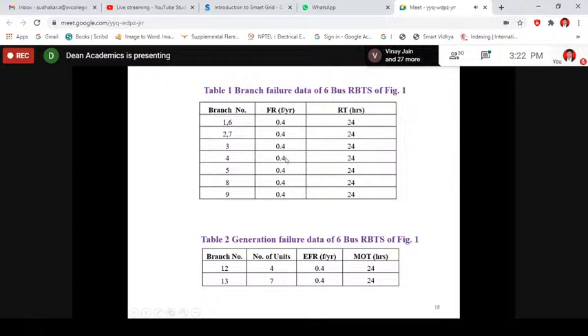Anyway, this is the estimated assumed value, and this is also the repair time for certain transmission lines. People may say 1 or 2 hours, but practically, if it fails in the evening, no repair will come immediately. You may have to wait around 12 hours until the next day when the lineman or electricians arrive, cut supply to the other zone, and so on. We are not doing live replacement here, although it exists in the world; some countries use it, especially in high voltage systems where they cannot shut down the power supply, so live replacements have been made with appropriate protective systems. I know this from literature even two decades ago, but we are not doing those things here. So 24 hours has been randomly assumed.